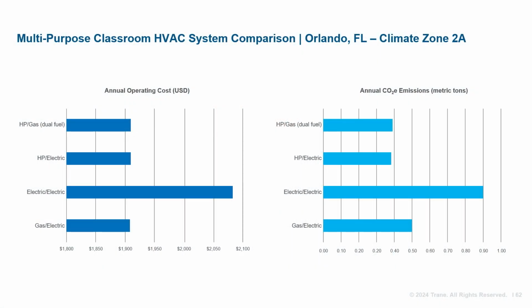Let's go through the 4 cities, starting with Orlando, Florida, looking at operating energy and CO2e performance. Orlando is a cooling dominant location with a small amount of heat required. As we look at the various locations in depth, we will use the gas-electric rooftop unit as our baseline system to compare to. There is not much difference in annual operating energy across the 4 configurations. However, when we look at CO2e, a heat pump with either electric or natural gas shows a reduction of 24% CO2e, when compared to a traditional gas-electric rooftop unit.